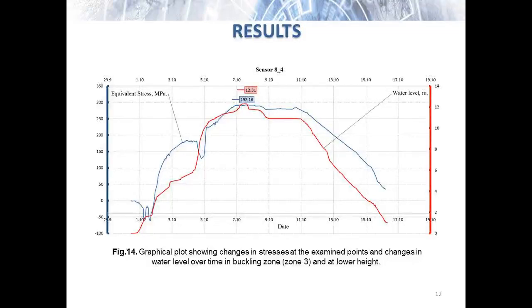After gathering and analyzing the results of the experimental study, the following conclusions can be drawn. Throughout the experiment, no critical strain value specified in normative and design documents was exceeded in any structural element or joint, which agrees well with the calculated results. The results of mathematical modeling, second stage, performed taking into account the characteristics of defects correlated with the in-situ measurements taken at all examined points. Correlation of the water level in the tank with the level of deformations at points along the shell height is traced. The results are consistent with the mathematical simulation data determined for the design version of the tank. The values of deformation at the very beginning of measurements and at their end differ within the measurement error. No strain accumulation was observed at all 32 measurement points. The tank returned to its original state, which was confirmed by calculations.